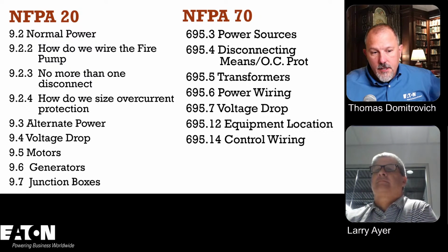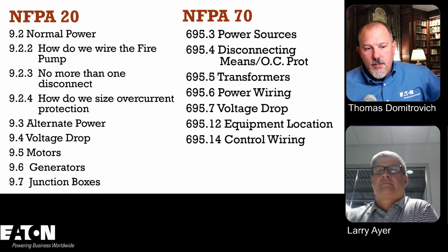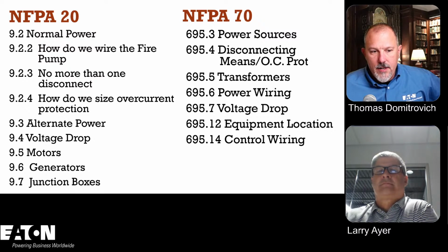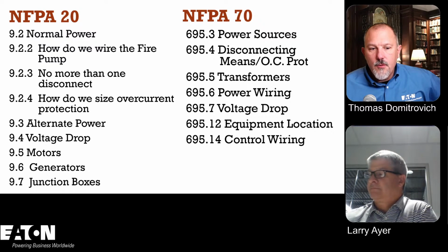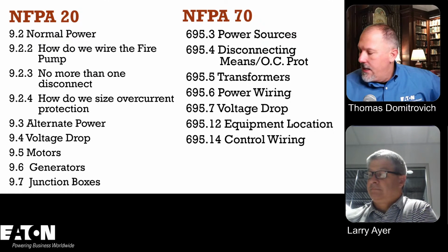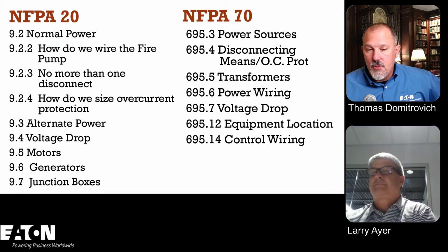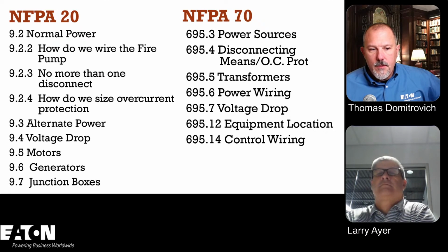Yep. There's a good discussion going on between Al Teresi and Brian Rock about the enclosure. So Al is saying, or an enclosure with an ingress protection, IP rating of IP31. And IP I always think of as like finger safe type of concept. And I think they're talking about the enclosure types and whether or not that's like a type 2 or whatever. And then Brian said, look at informational note number 2 on 110.28. That says IP ratings are not a substitute for enclosure type ratings, which I completely agree with. But then Al pointed out that that's NFPA 20. So, Larry, there might be a little correlation issue between NFPA 20 when it comes to the enclosure types that you can use. That's something to think about.